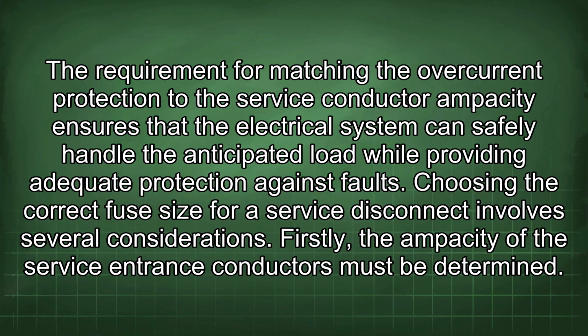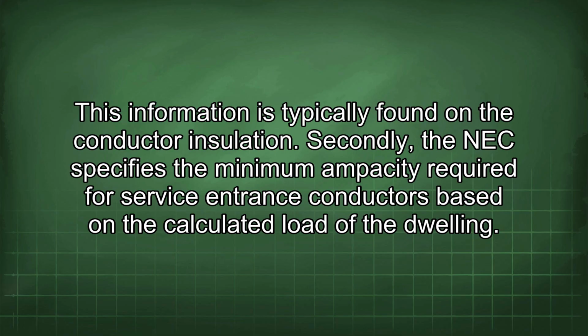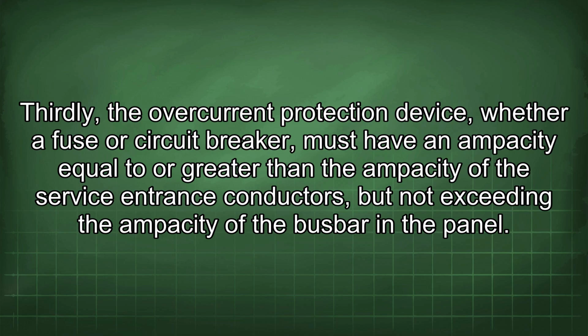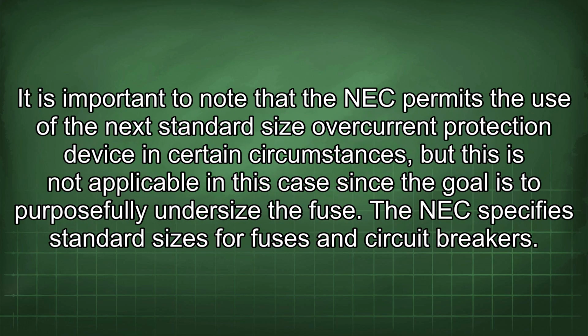Choosing the correct fuse size for a service disconnect involves several considerations. Firstly, the ampacity of the service entrance conductors must be determined. This information is typically found on the conductor insulation. Secondly, the NEC specifies the minimum ampacity required for service entrance conductors based on the calculated load of the dwelling. Thirdly, the overcurrent protection device, whether a fuse or circuit breaker, must have an ampacity equal to or greater than the ampacity of the service entrance conductors, but not exceeding the ampacity of the busbar in the panel. It is important to note that the NEC permits the use of the next standard size overcurrent protection device in certain circumstances, but this is not applicable in this case since the goal is to purposefully undersize the fuse.